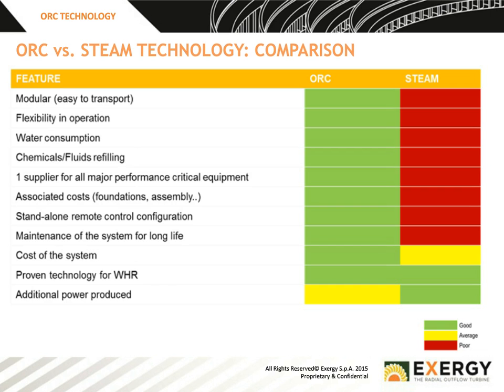Water consumption. By using an organic fluid, which is a closed loop, and by having an air cooler, it's possible to have a plant with no steam, no water consumption whatsoever. The fluid consumption of these plants is very, very small and is simply brought in as a spare fluid, usually in a container every year, every 2 years, something like that. So again, for chemicals, for fluids refilling, there's very, very little to talk about with ORC. It really is a standalone, low-maintenance type of unit, more like an air conditioner than a typical Rankine cycle system.